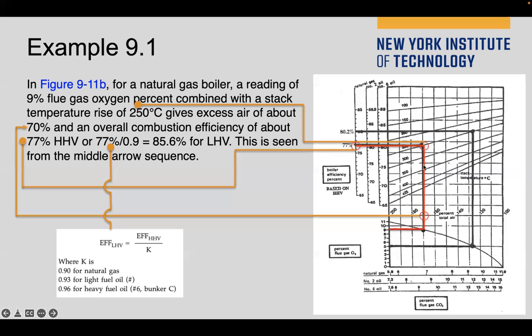Okay, so we have another point. We need to put a stop where they intersect the stack temperature. After we put this stop, we need to draw a vertical line. Why 250? Because here is 250, okay. And the horizontal line, then we draw vertically and touch with, depends on what fuel you use. If you use natural gas, this line will be what we need to take a look.